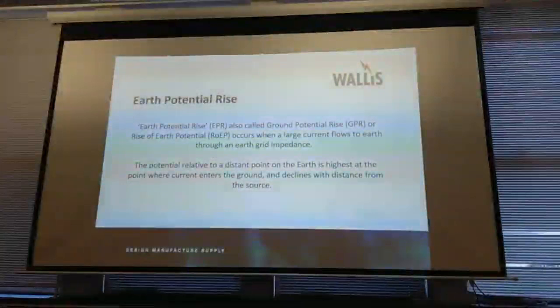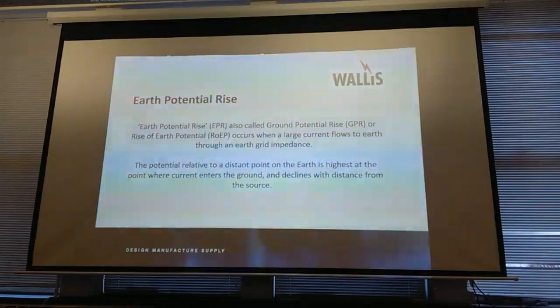So I've got an 11 kV cable in my hand. I'm going to touch that to the earth system. That phase to earth is going to be 6,350. It is actually going to energise the ground we're standing on to 6,350 volts, working on a 0 ohm network. Between there and there, you will have a difference in potential because the ground is a resistor. So when there's resistance, there's this potential difference. You might have 6,350 there, you might have 5,000 volts there. It's all down to the ground makeup again.